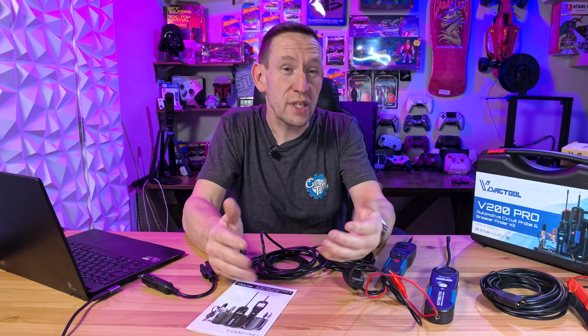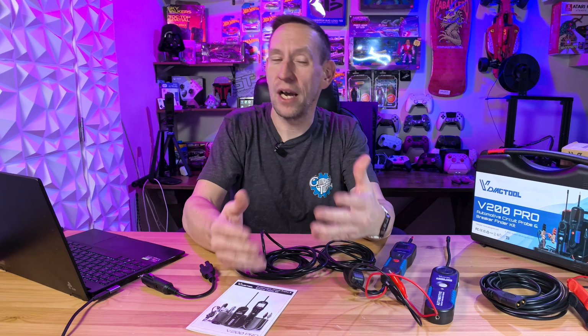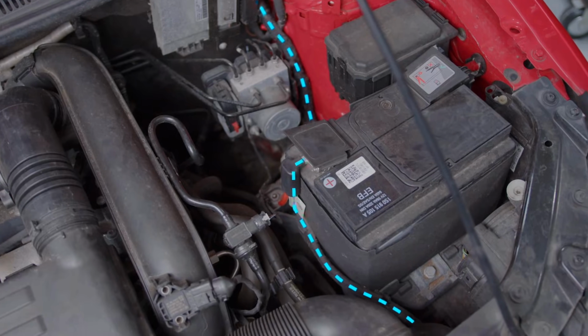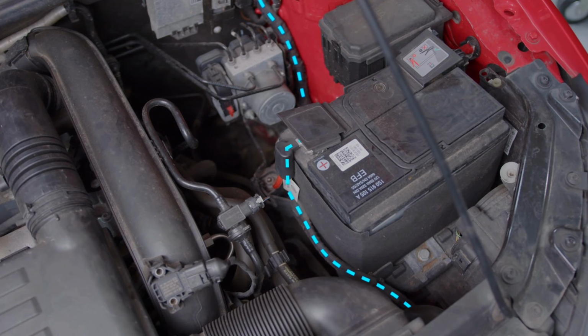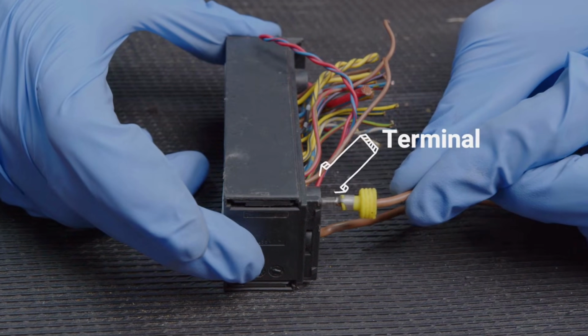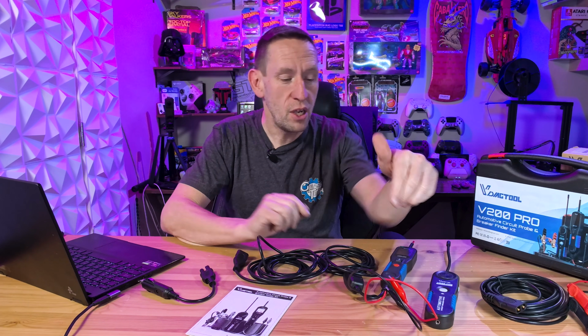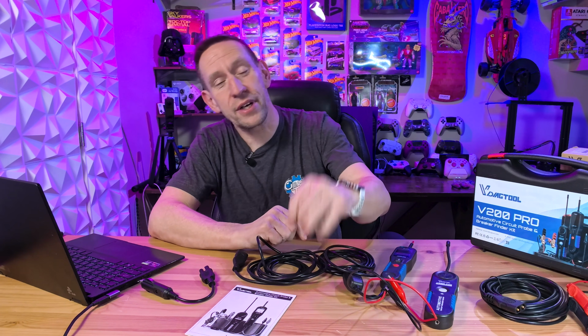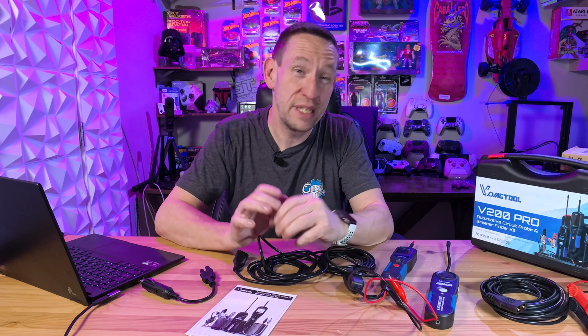Assuming that motor works, then you know the problem is upstream. It's not the motor, it's something in the controlling circuit. Could be that broken wire, could be a bad relay, could be a bad switch, but we can go backwards through here to figure out exactly which component is failing.